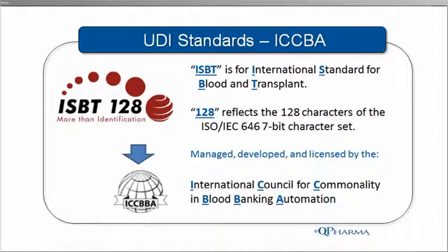The third major UDI standard is ISBT 128. ISBT stands for International Standard for Blood and Transplant, and the 128 is the number of characters it can contain. This standard is widely used by services and products related to blood, blood products, and organ transplants.